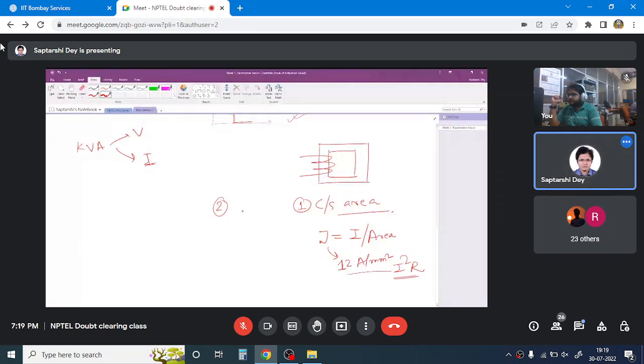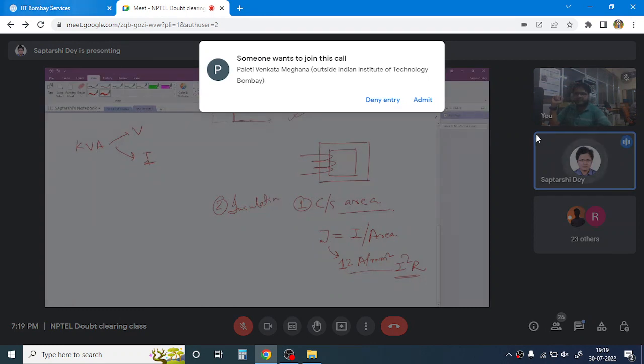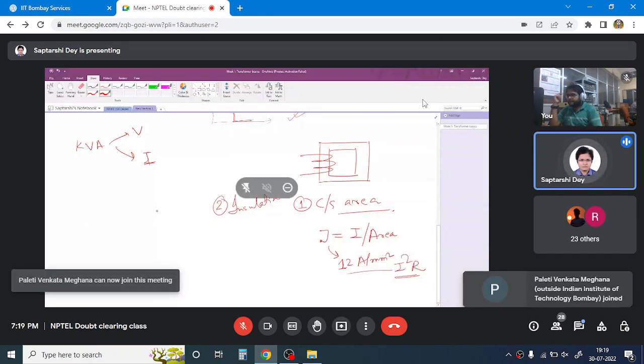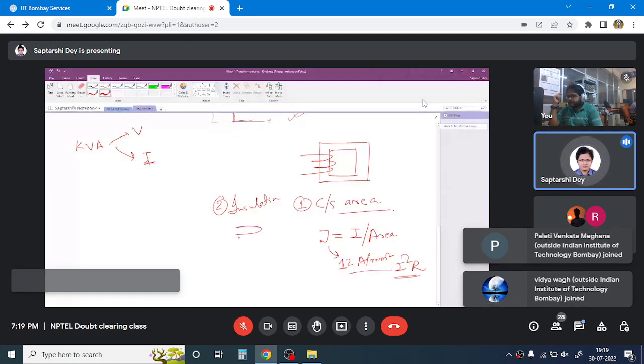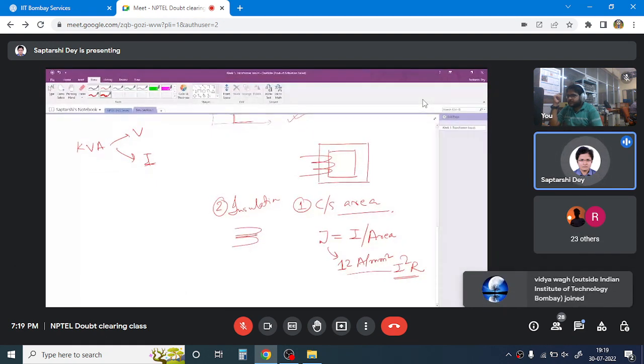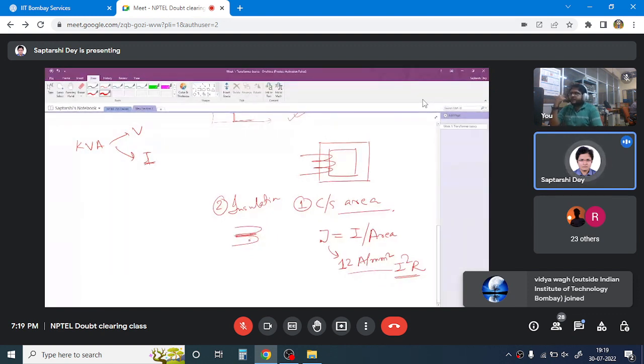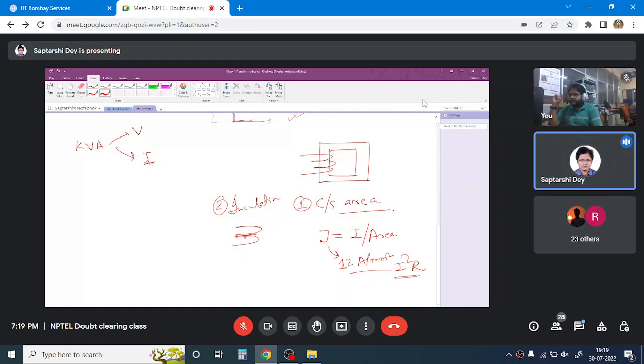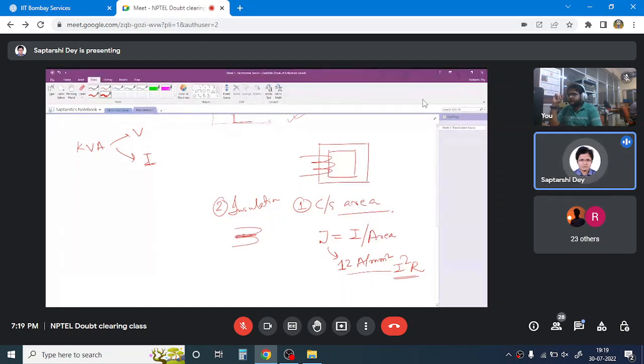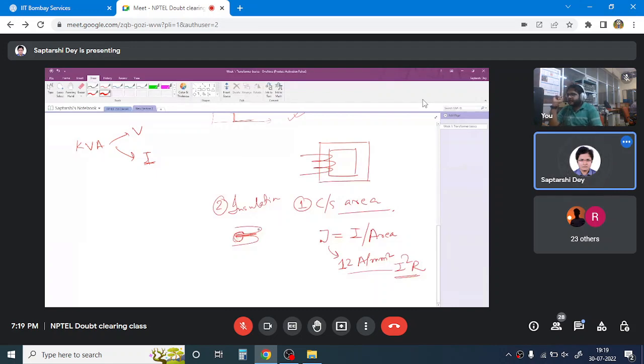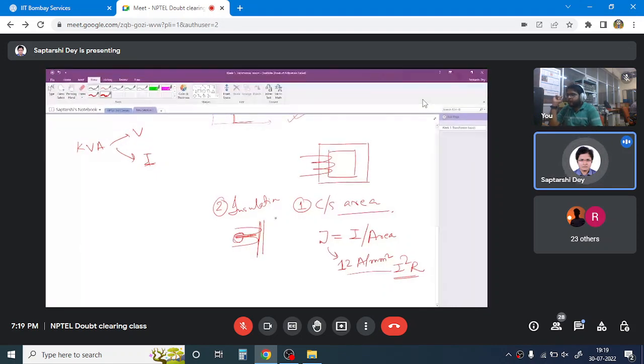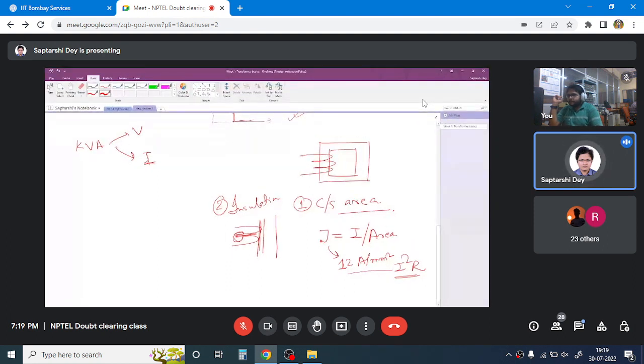Second thing is the insulation. Two insulations are mostly there. Firstly, in the winding, this is one turn, this is another turn, so there must be some insulation. This insulation must be able to defend the turn-to-turn voltage. There is a voltage per turn, it must be able to withstand. And secondly, the insulation between the winding and the core. If the core is grounded, then this insulation should be able to withstand that much voltage, the rated voltage. So as soon as you have given certain insulation to the transformer, your voltage rating is fixed.